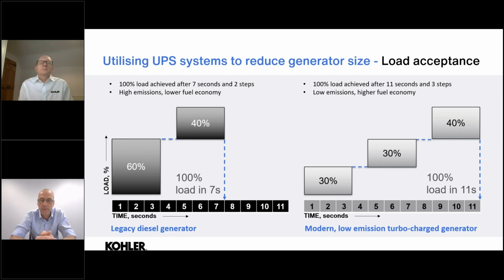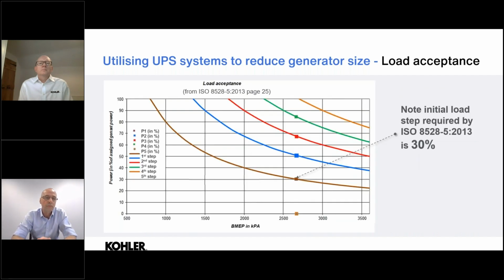are built to an ISO standard, which means they are designed to have these smaller load steps. And we see an example here. So over the first 3 seconds of just 30% load step, another 30% load step, and 40%, stepping it in over 11 seconds rather than the 7 seconds. So the ISO standard, ISO 8528, outlines the requirements from the generator as a minimum. Okay, and this is what the modern engines are designed to meet. So we need to take that into account when we're actually designing the data center and the load acceptance.